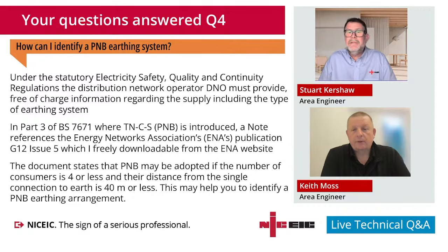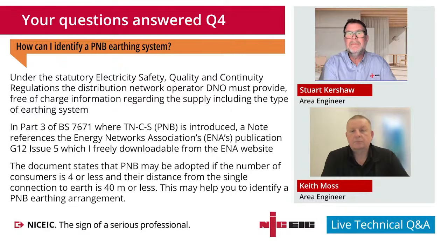Definitely. And it's basically earth outside of the consumer's installation. I suppose that length of cable is shorter, so the rate of rise for the voltage to true earth would be reduced. Or is that the premise behind that, do you think? Yeah, and I think the fact that it's limited to 4 consumers, so the perceived risk isn't as high if you lose the neutral. Yeah.